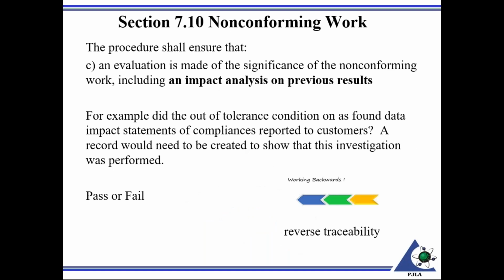C, the procedure shall ensure an evaluation is made on the significance of the non-conforming work, including an impact analysis on previous results. So, for example, on those out of tolerance conditions on the artifact that was sent in for calibration, did the as found data impact statements of compliance you may have made to the customer in the reports issued to them? That's when you stated perhaps a sample pass or a specific artifact was in tolerance, when in fact this out of tolerance condition, if incorporated into the test or calibration, may possibly jeopardize that from being true.